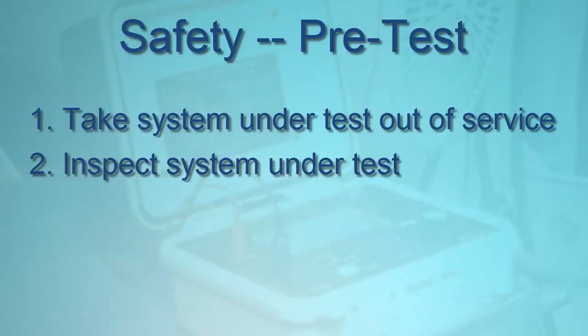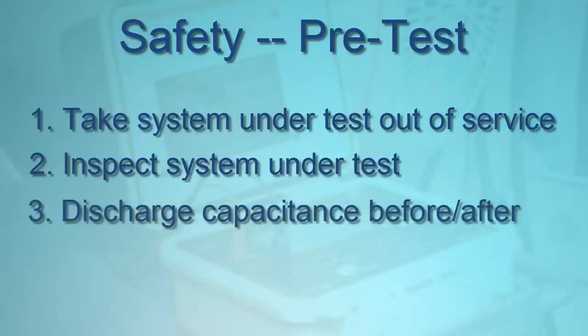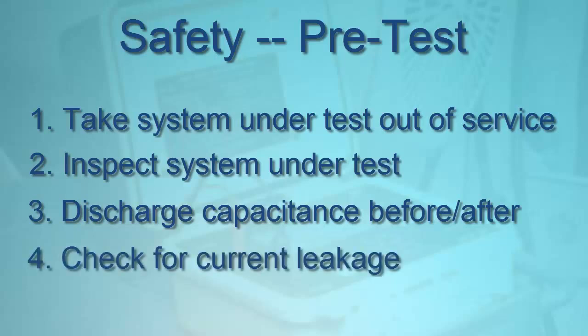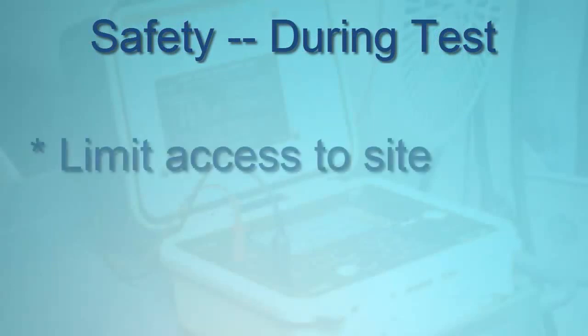Also, be sure to discharge capacitance before and after conducting an insulation resistance test. Note that AEMC megohmmeters automatically discharge capacitance when not running a test. Finally, check current leakage at switches and other connections. When performing the test, restrict personnel access to the test site.